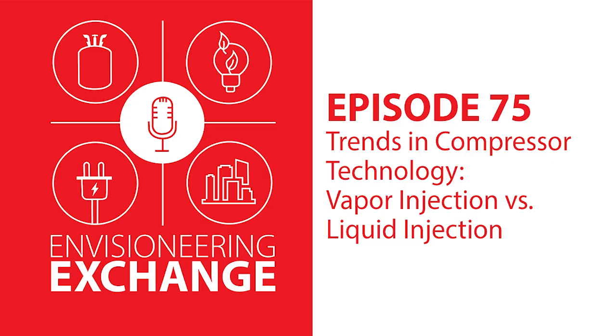So when we talk about liquid injection, as you mentioned, it has been around for a long time too, and it has some benefits and some drawbacks as well. One of the main benefits with liquid injection is that you do a similar thing. You're taking a line off the condenser coil, and you have some sort of expansion valve that's modulating the liquid flow into the compressor. And then you have a feedback loop based on your discharge gas temperature.